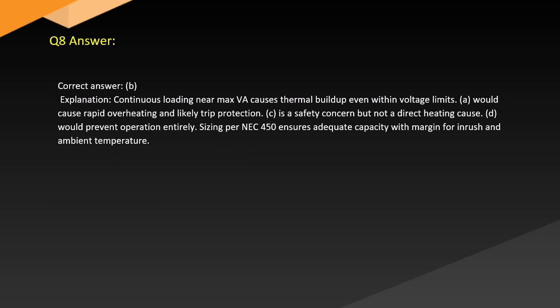Answer. Correct answer: B. Explanation. Continuous loading near max VA causes thermal buildup even within voltage limits. A. Would cause rapid overheating and likely trip protection. C. Is a safety concern but not a direct heating cause. D. Would prevent operation entirely. Sizing per NEC 450 ensures adequate capacity with margin for inrush and ambient temperature.